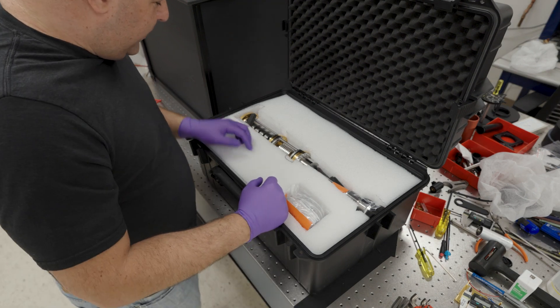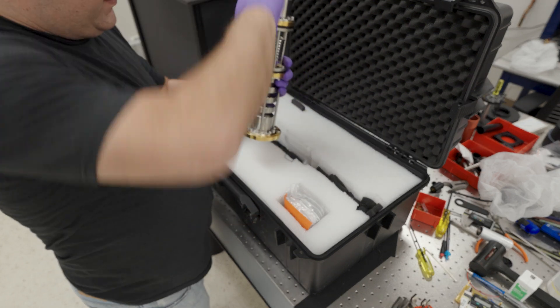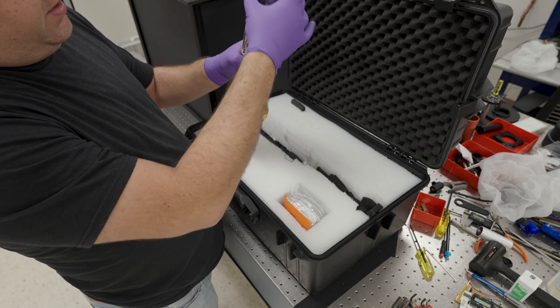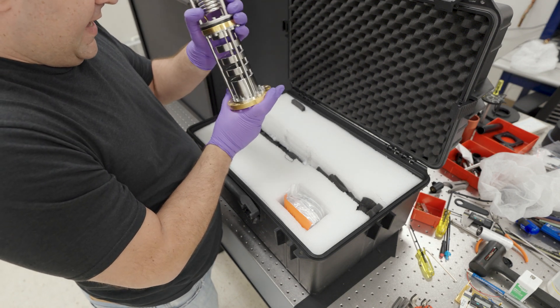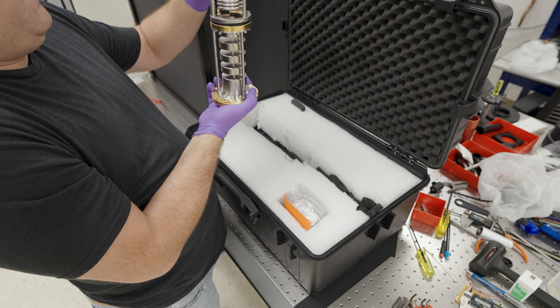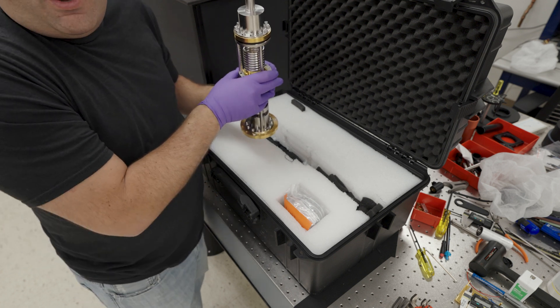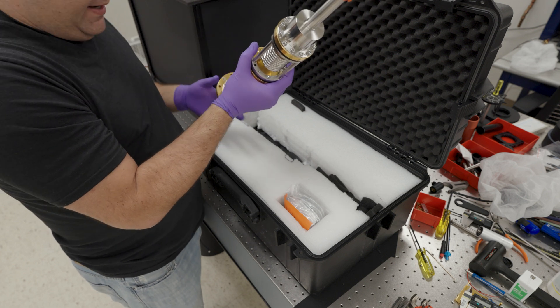Here it is — the beating heart of the dilution refrigerator, the dilution unit. We can pull it out and take a quick look. So there is this bellows here. Gas comes in here; this bellows is for vibration isolation. This is the still. I don't know where the gas gets injected. This is the stepped heat exchanger — this is where it gets cold. This is the still up here. It looks nice. Maybe this isn't the heart of the dilution refrigerator — it might be the guts — because this is what takes the gas and pipes it around and makes it work.